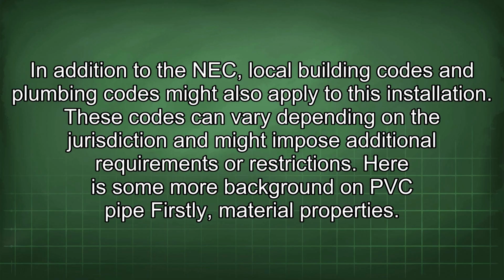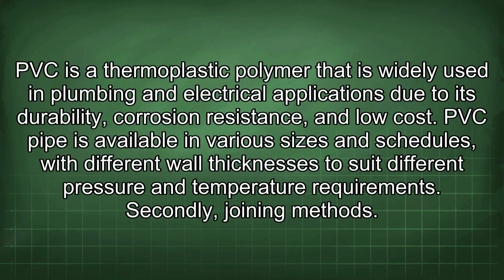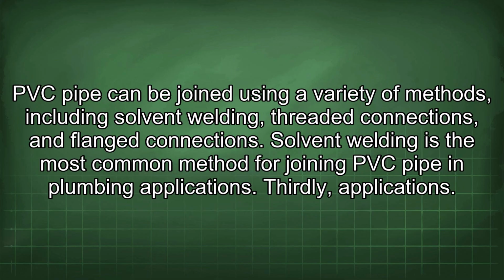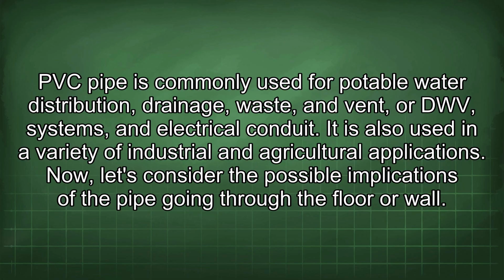Firstly, material properties. PVC is a thermoplastic polymer that is widely used in plumbing and electrical applications due to its durability, corrosion resistance, and low cost. PVC pipe is available in various sizes and schedules, with different wall thicknesses to suit different pressure and temperature requirements. Secondly, joining methods. PVC pipe can be joined using a variety of methods, including solvent welding, threaded connections, and flange connections. Solvent welding is the most common method for joining PVC pipe in plumbing applications. Thirdly, applications. PVC pipe is commonly used for potable water distribution, drainage, waste, and vent, or DWV, systems, and electrical conduit. It is also used in a variety of industrial and agricultural applications.